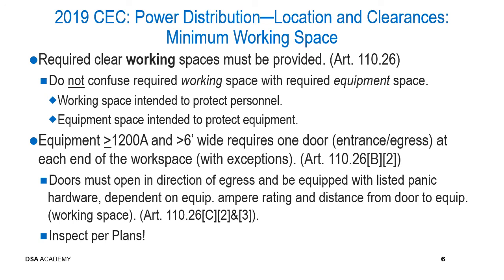110.26. Now, equipment that is greater than or equal to 1200 amps and is also greater than 6 feet wide requires one door, which is going to be understood to be the entrance or the egress at each end of the workspace. Now, there are exceptions to this, and you can review these exceptions in Article 110.26(B)(2). However, again, with most issues relating to electrical construction, the electrical engineer and the design team are going to do their homework. They're going to verify that whatever is approved by them for installation on the project is actually safe and compliant with the code.